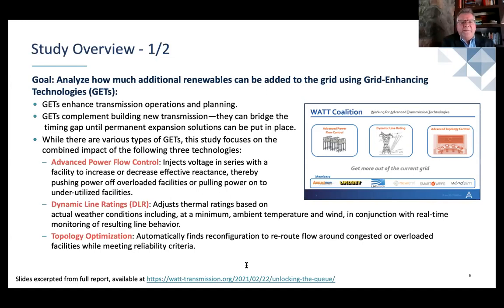They change the effective impedance of the transmission system in a way that you can add impedance, which would become an increased barrier to flows and actually lower the flows on critical elements. Or you could actually lower the impedance of a transmission line that would pull power from other lines across underutilized facilities. The last type of grid enhancing technology we look at in this study is topology optimization.